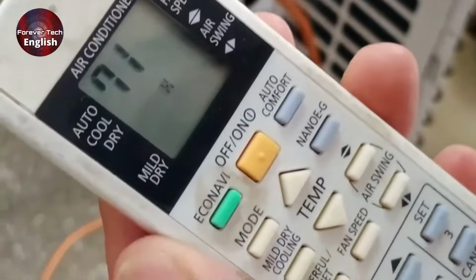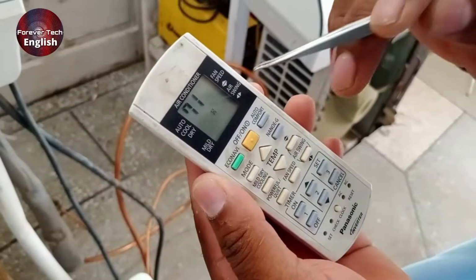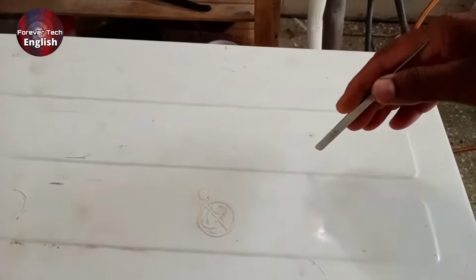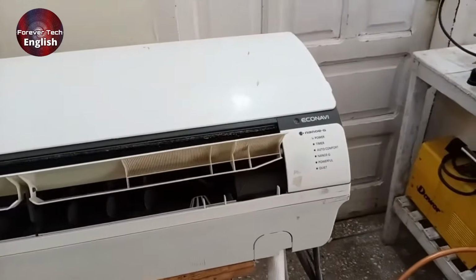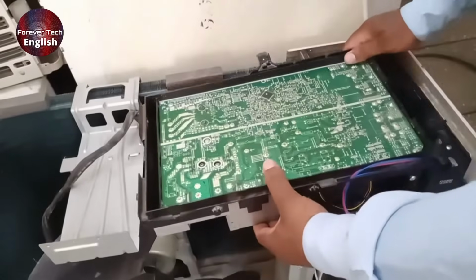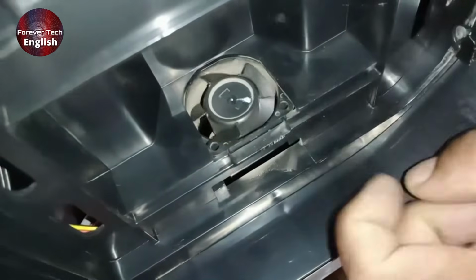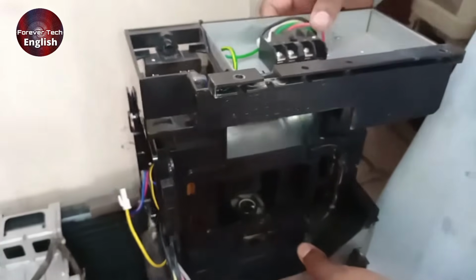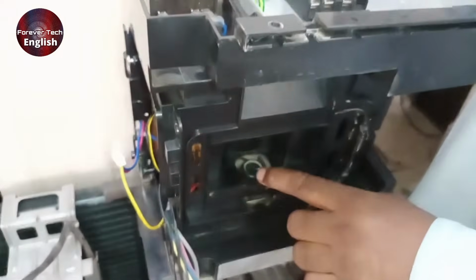H71. This means there is an issue with the PCB in your outdoor unit, and the cooling fan of your outdoor unit's PCB has become faulty. Let me show you the cooling fan. After fully opening the outdoor unit's PCB, you can see the cooling fan here. If this fan becomes faulty, your DC inverter indoor unit will give you either an H71 or H87 error.